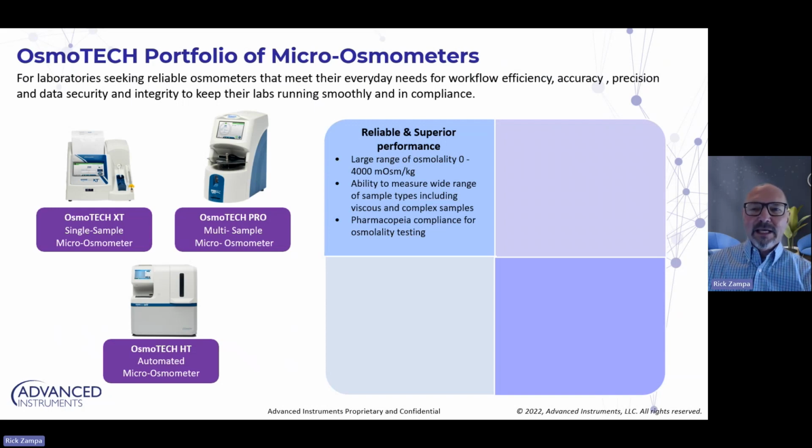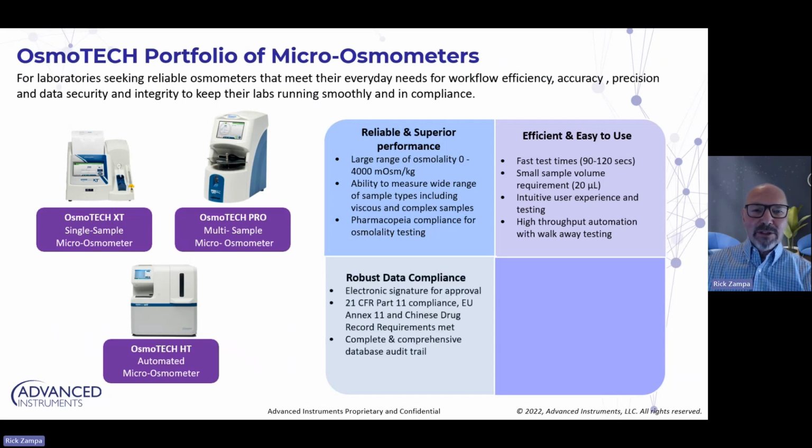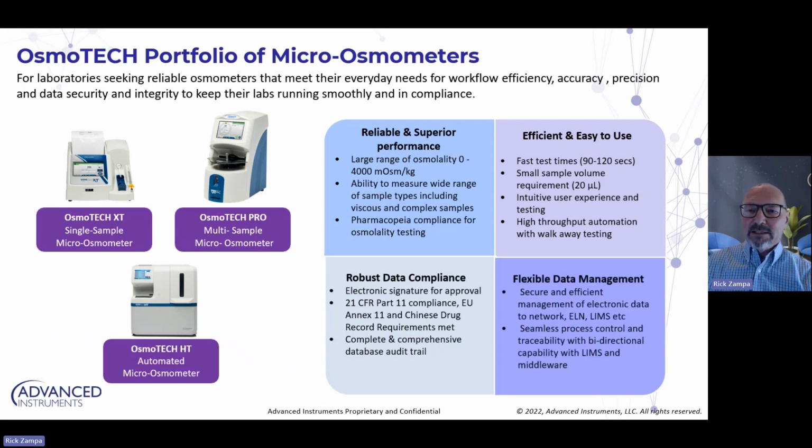With our Osmotech XT device, we provide osmolality testing up to 4,000 milliosmoles, which is perfect for those higher concentration or more viscous solutions. The testing process is fast, and each is simple to integrate into any customer workflow and throughput of testing. They have flexible data connectivity options and strong data integrity features, which are adjustable to your lab's specific needs and are therefore flexible for R&D, process development, and manufacturing settings.